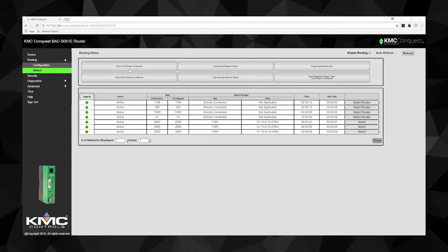The Send I Am Router to Network button can trigger inter-network-wide updates by sending an I Am Router to Network message to all networks. Send Whois Router Network initiates a query to other routers that results in a discovery of other networks. These other routers respond with a BACnet I Am Router to Network message, and if a new router responds, it is added to the route list.